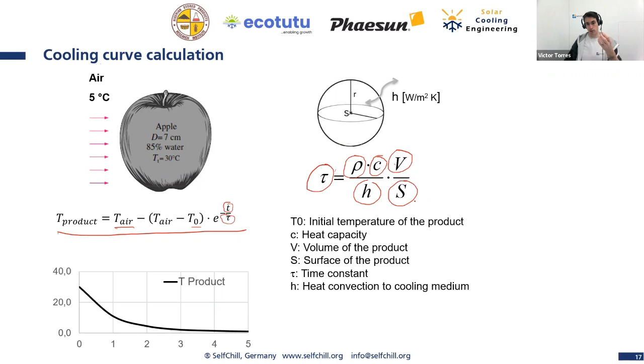So the calculation of all these parameters in this equation gives us a feeling of how fast the product will cool down. If you have a watermelon that is this big, you can calculate here and you will see the cooling curve is quite slow. For this case, you might need a pre-cooling chamber, or perhaps you want to use cold water to cool down the product quicker. So we need to understand this so that we can recommend our final users to use one pre-cooling method or another. I'm not going to go into detail on this today, but we are having a look at the equation so that you have in your hand how to estimate this cooling curve.